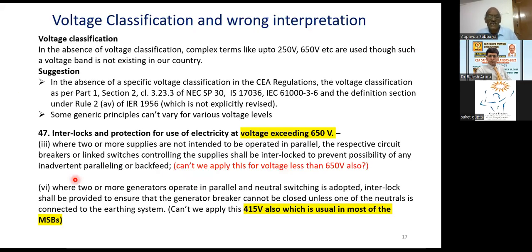Another thing is, where two or more generators operate in parallel, they should ensure a neutral switching arrangement. Here, it is only a choice. You need not have a neutral switching arrangement compulsorily. You can provide single pole, single point earthing also. Here, it is coming under the 650 volt, exceeding 650.